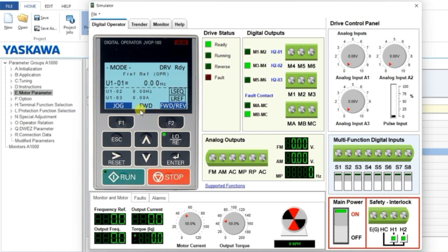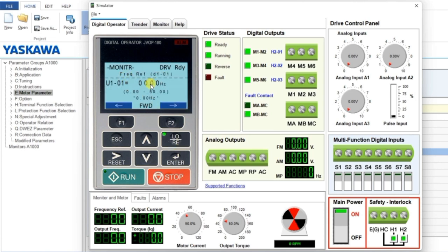Now we will be able to operate the VFD from the keypad. First, click on the Run button. You may not see the motor running yet - for that, look at 'Frequency Reference' and click Enter. It will ask for a frequency input. Use the cursor buttons to navigate, then use the up/down buttons to change the frequency.